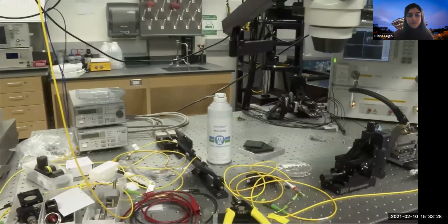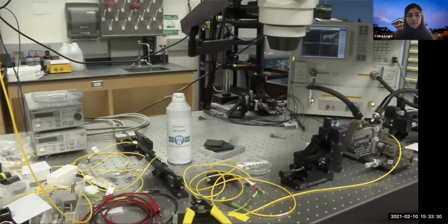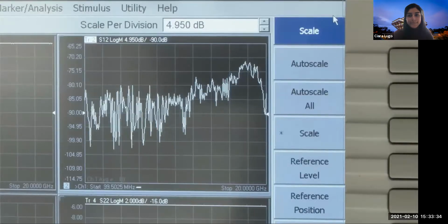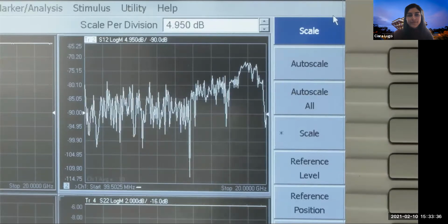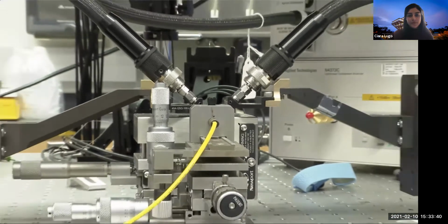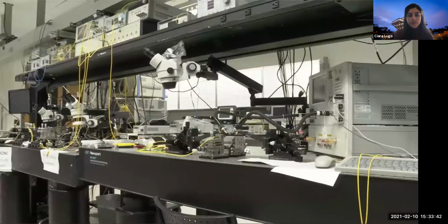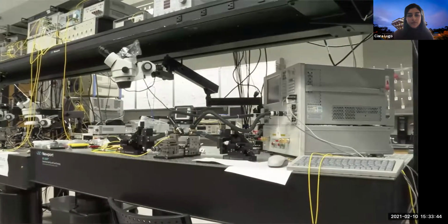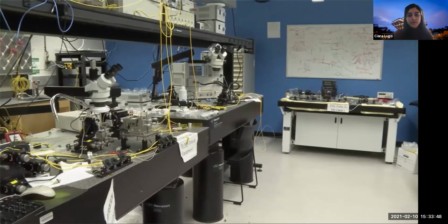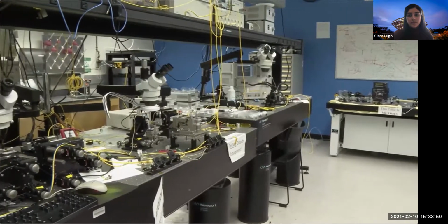This lab bench is used for S-parameter characterization in all four primary configurations: electrical-electrical, electrical-optical, optical-electrical, and optical-optical via an optical network analyzer. This is a powerful tool primarily used when sensitive characterization of high-speed devices is needed. This tool is often used to characterize modulators and detectors.